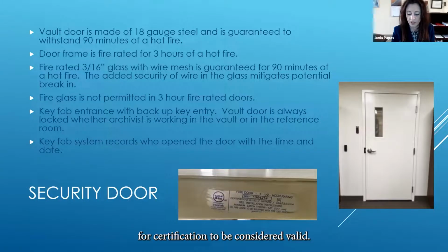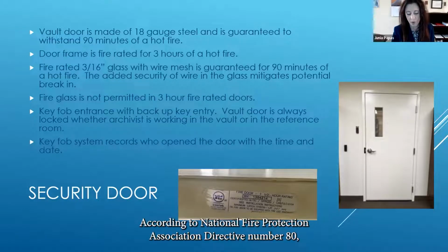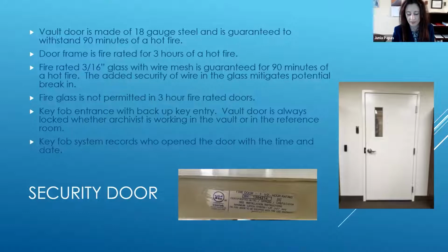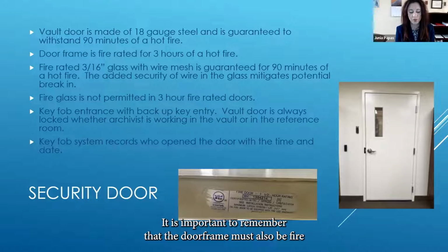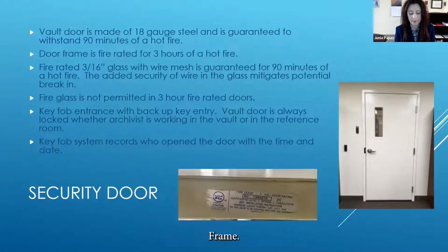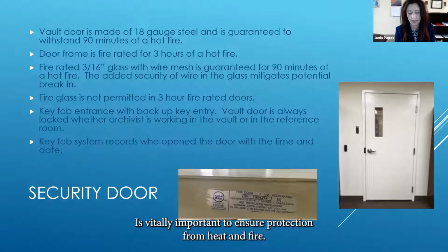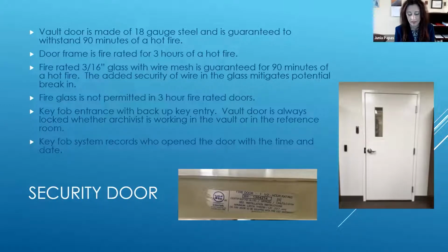For certification to be considered valid, the doors and frames must be installed according to National Fire Protection Association Directive number 80, which is the standard for fire doors and other opening protectives. It is important to remember that the door frame must also be fire rated. Not just the door and the wall, but the frame is vitally important to ensure protection from heat and fire. Our door frame is rated to withstand 3 hours of a hot fire.